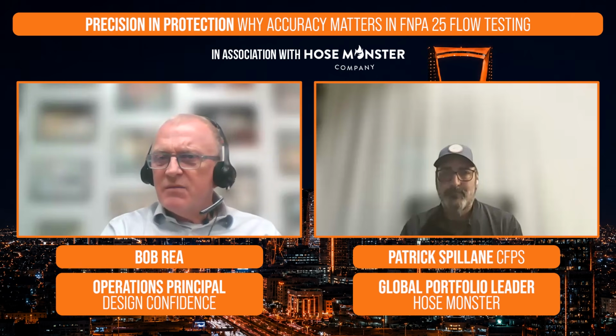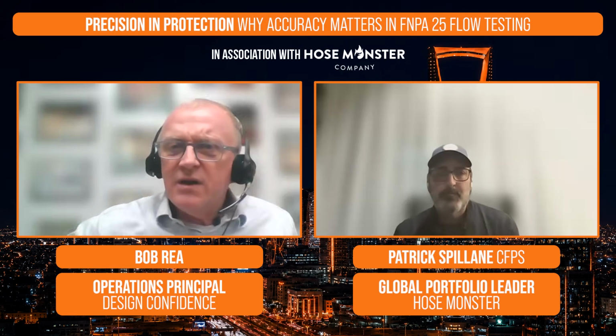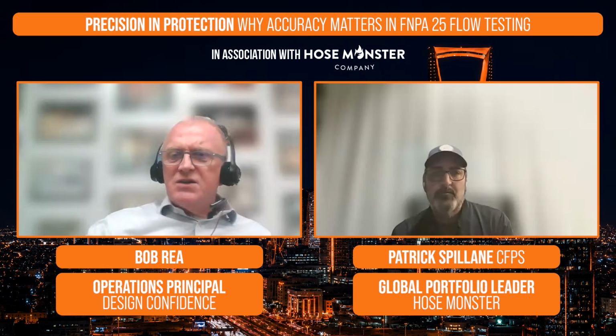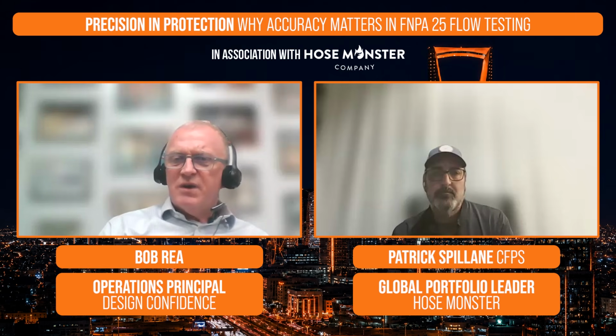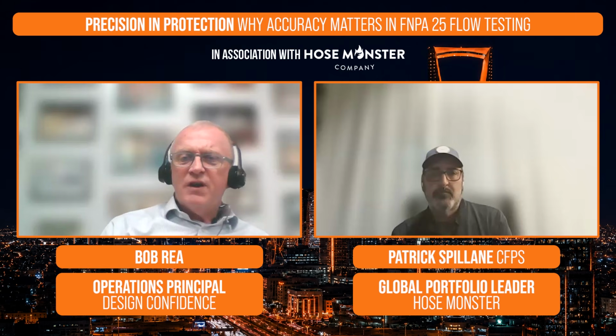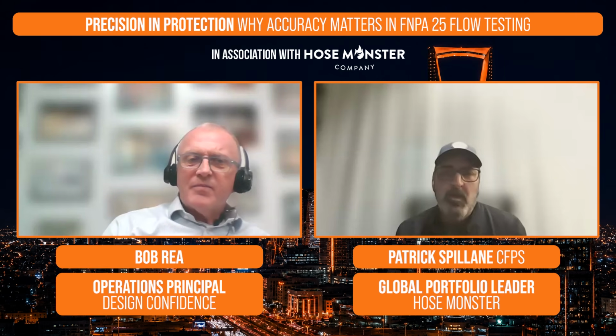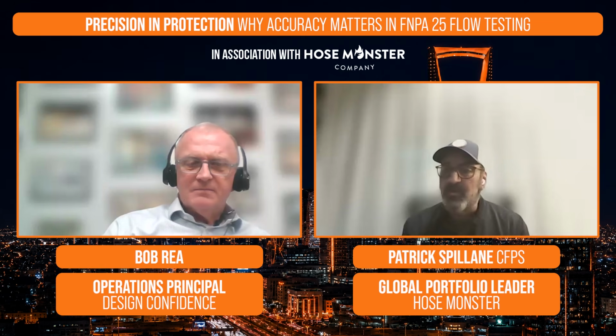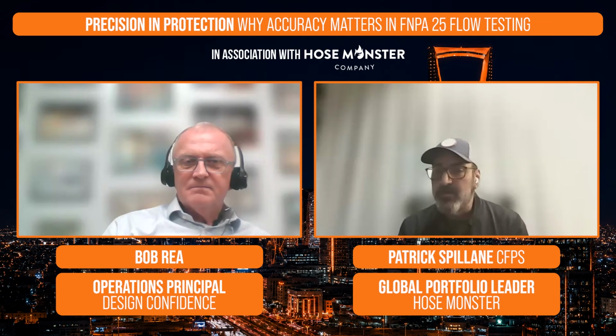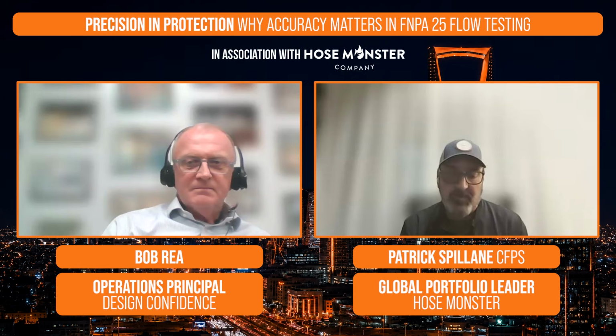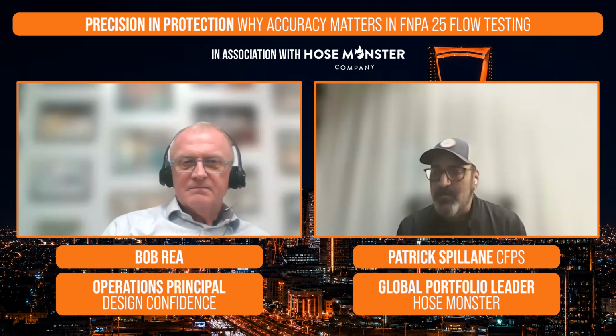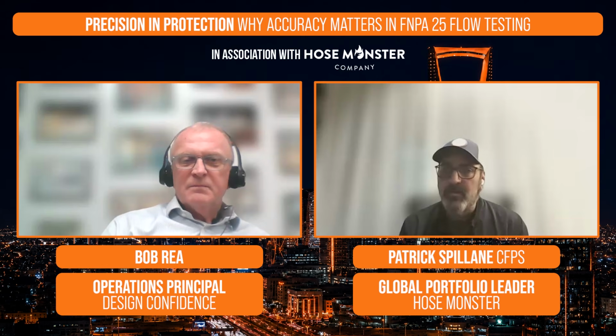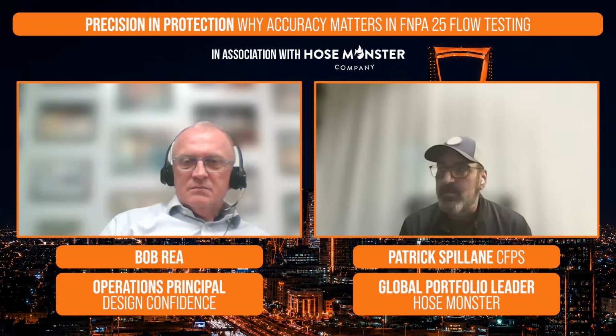You've got one coming again, Abdullah. Basically, I thought we'd covered most of that. If we notice abnormal readings during the churn test, what should the next step be before deciding if a full flow test is required? Well, the full flow test should be done every year, at least annually. You can flow, especially with a flow meter. There's nothing stopping you from flowing that fire pump more than annually, if you really want to put it under a load. But yes, you should be doing it at least annually.